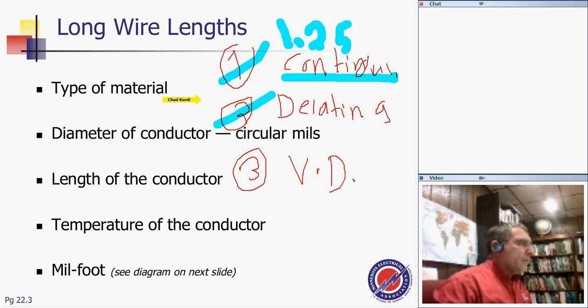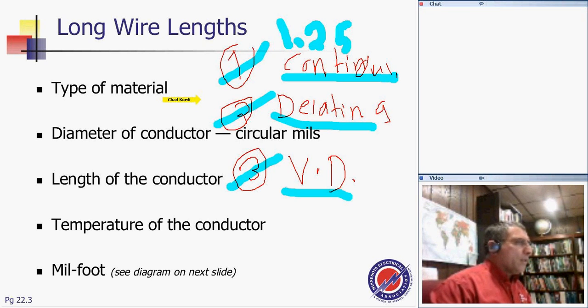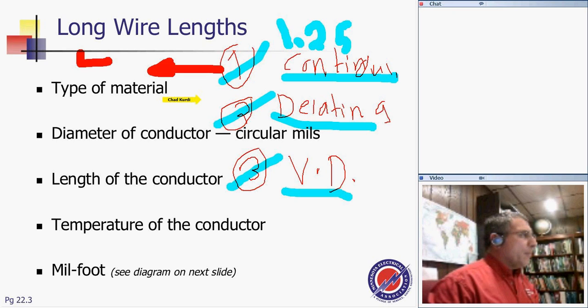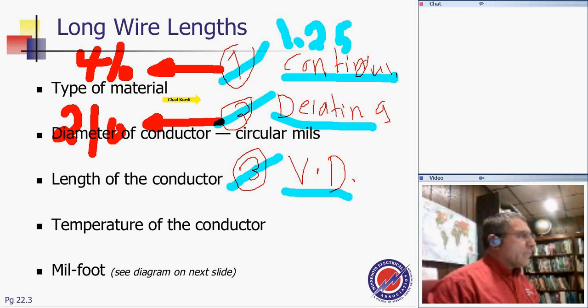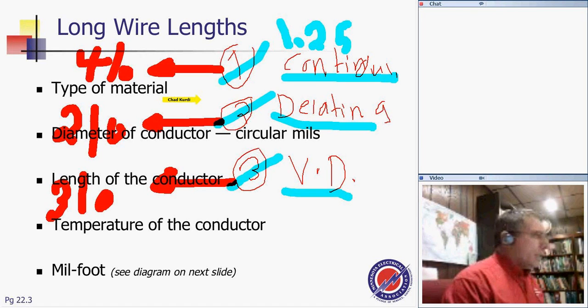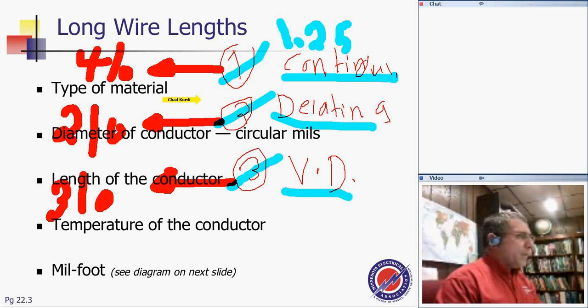Then, do I have to derate? Are there factors involved? If yes, you have to derate. Voltage drop. Do I have to do voltage drop? Are there longer distances? Am I running 100 feet or more, where I have to pay attention to voltage drop? Then I have to size based on voltage drop. So when you size based on continuous load, you came up with 4/0. When you do the derating, you came up with 2/0 for the load. And suppose when you did a voltage drop calculation, you came up with 3/0. Same amount of load. Can you see that? Three different separate calculations came up with 3 different answers.